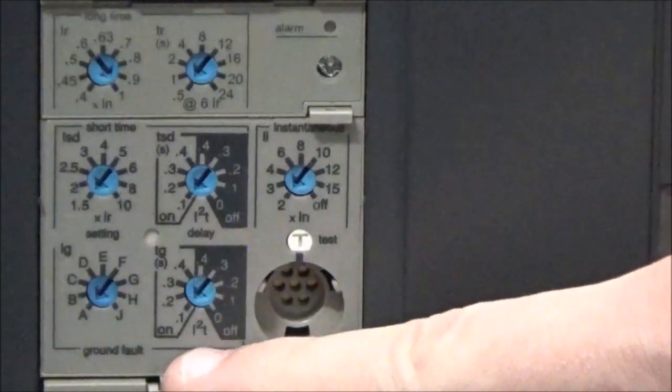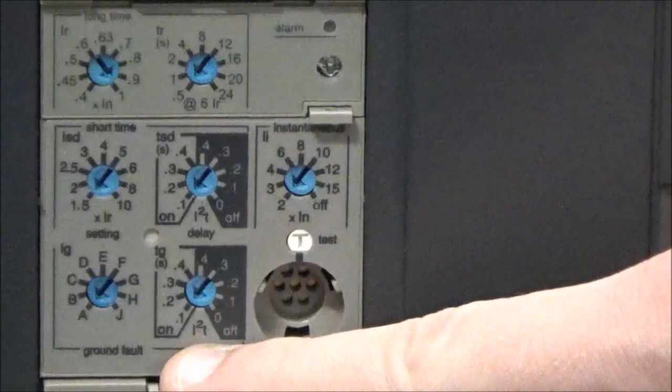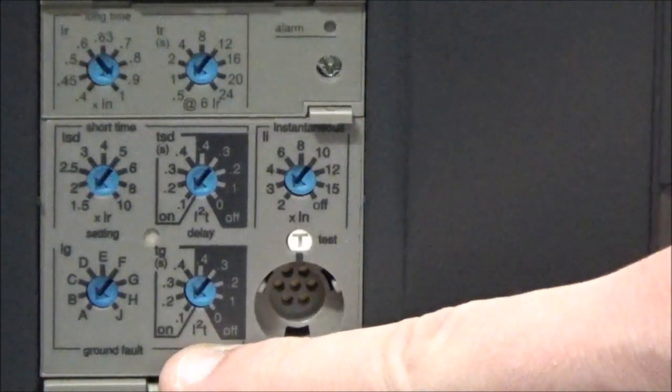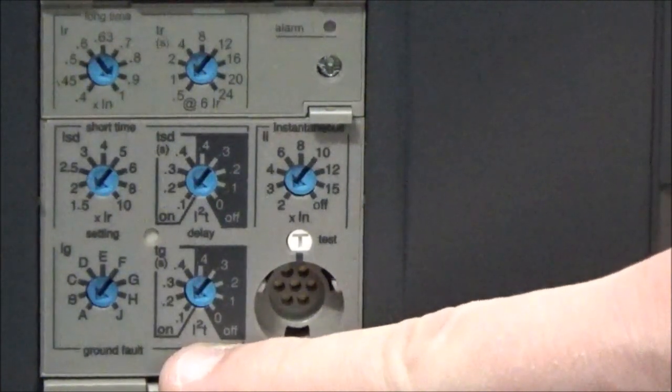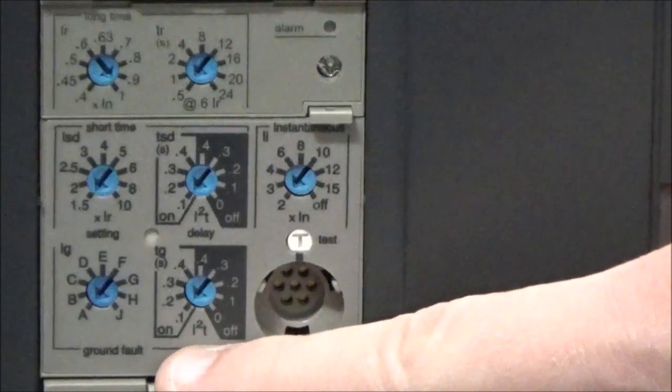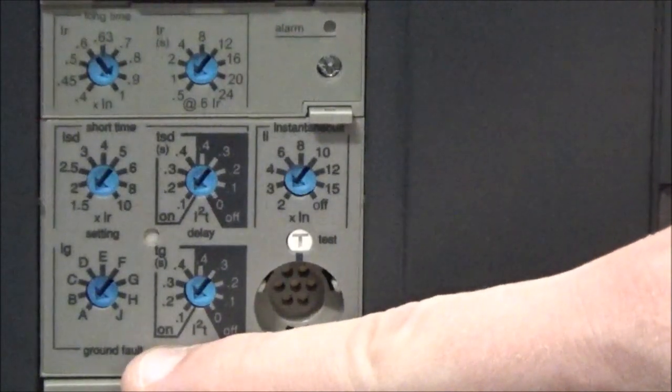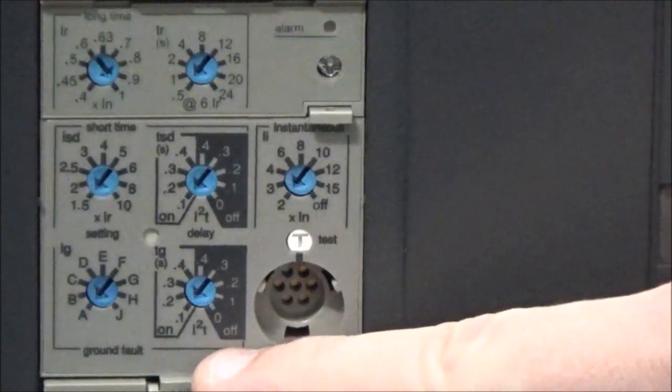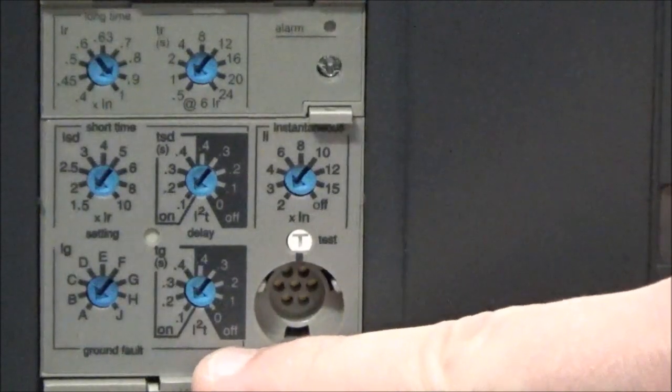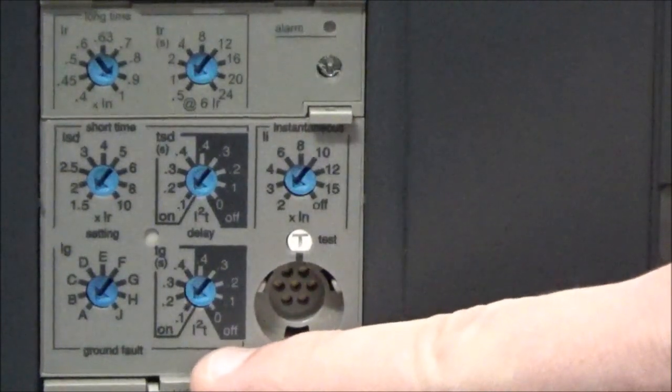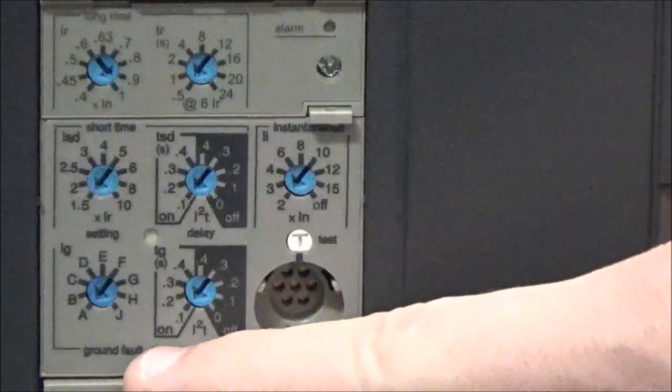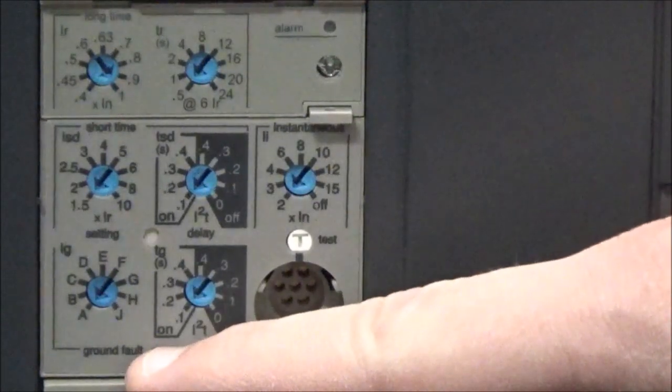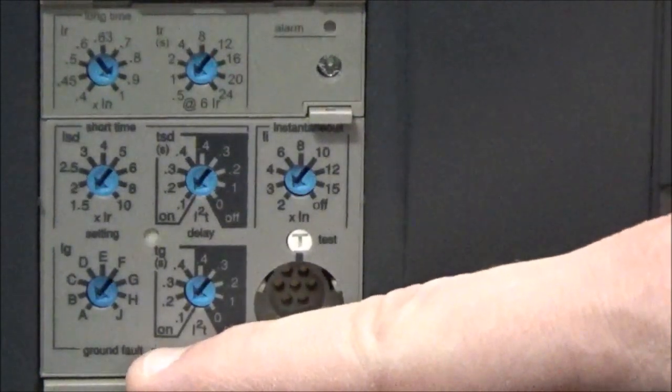For the ground fault delay, it is similar to the TSD short time delay setting in that it is in seconds and it has a non-shaded on side and a shaded off side. Again, you will use the shaded off side when using zone selective interlocking and the non-shaded on side when not using zone selective interlocking.